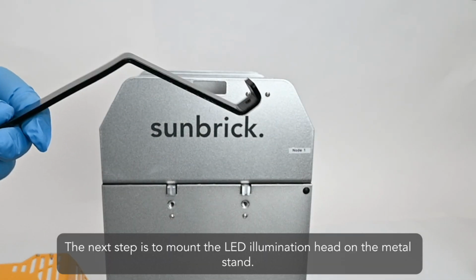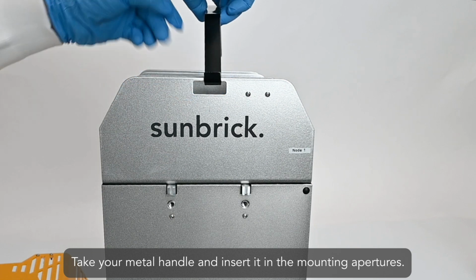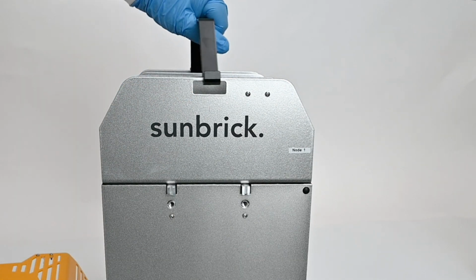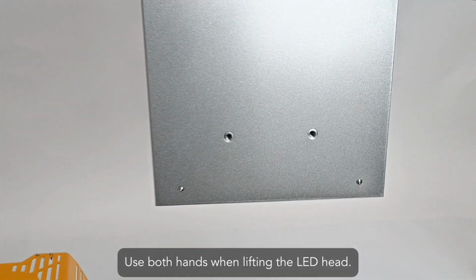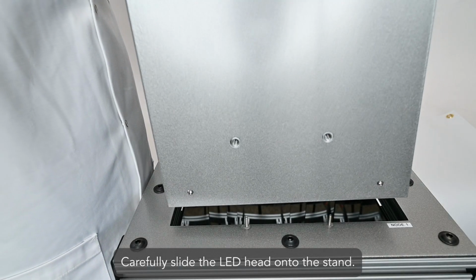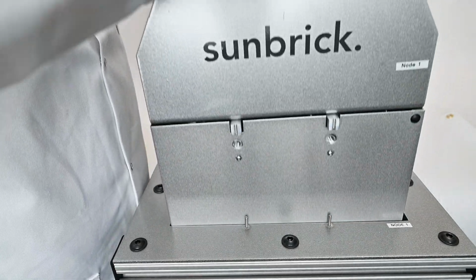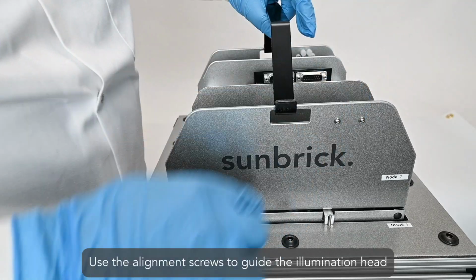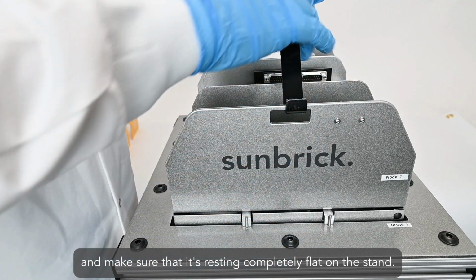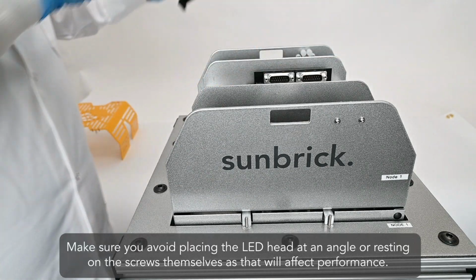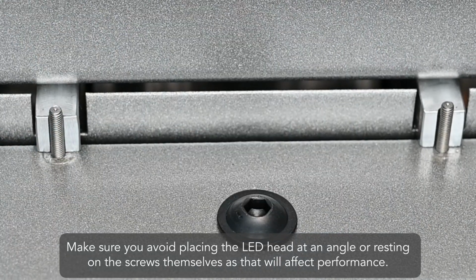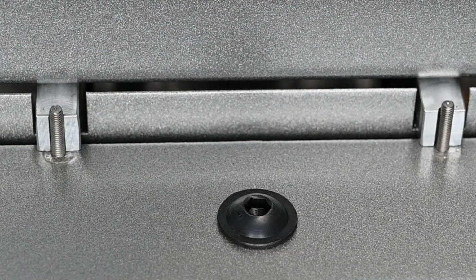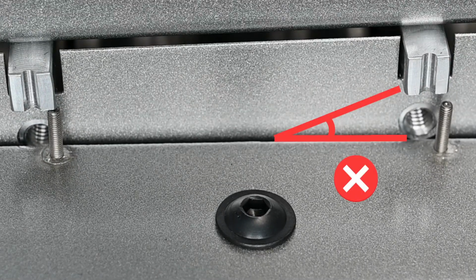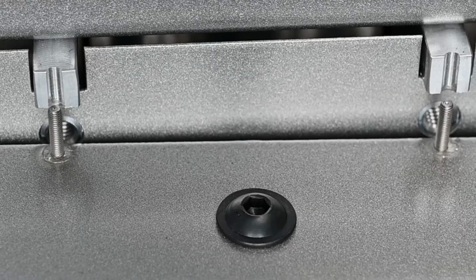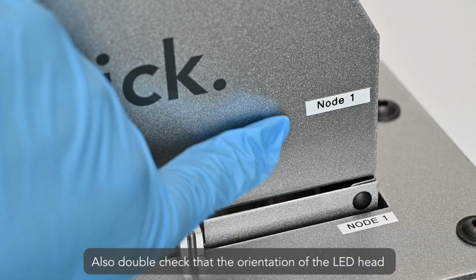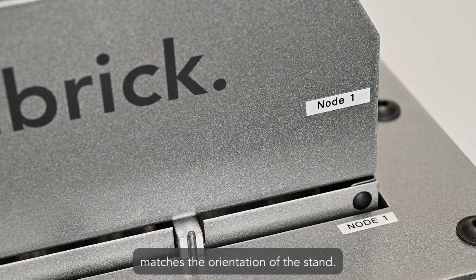The next step is to mount the LED illumination head on the metal stand. Take your metal handle and insert it in the mounting apertures. Use both hands when lifting the LED head. Carefully slide the LED head onto the stand. Use the alignment screws to guide the illumination head and make sure that it's resting completely flat on the stand. Make sure you avoid placing the LED head at an angle or resting on the screws themselves, as that will affect performance. Also, double check that the orientation of the LED head matches the orientation of the stand.